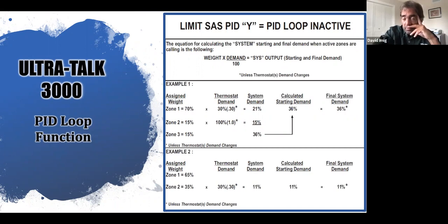Now understand that in either one of these examples, I start at 36% because 2 zones are calling. So I start in first stage. If I happen to get into second stage and one of those zones satisfies, my system demand immediately drops because it loses the value of the other zone, and it's now operating based on its own value. I do not need all that firing rate to meet that target temp for one zone.